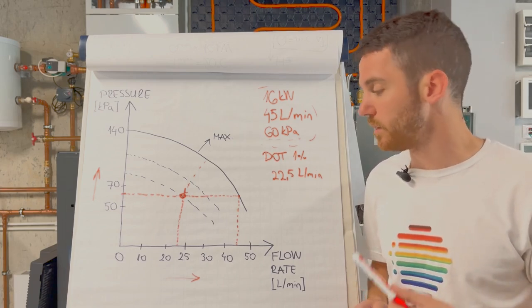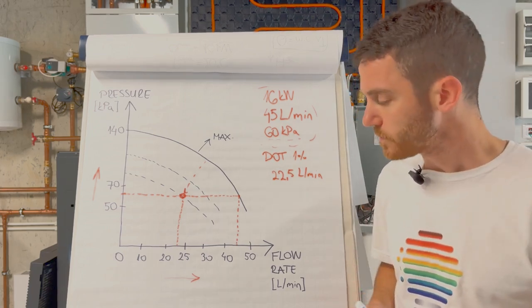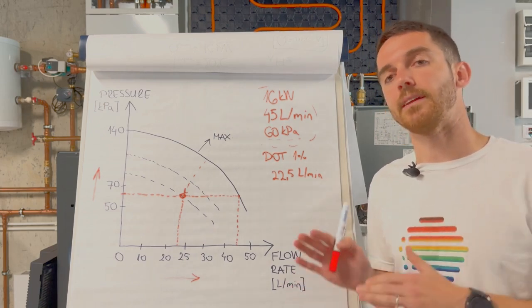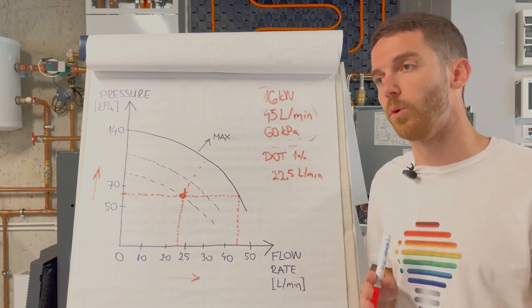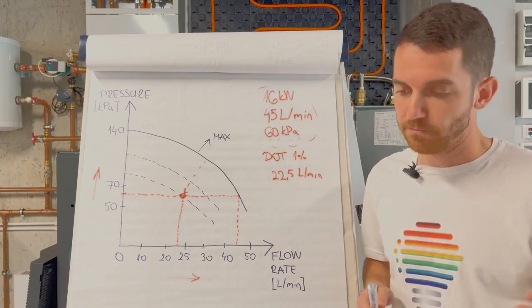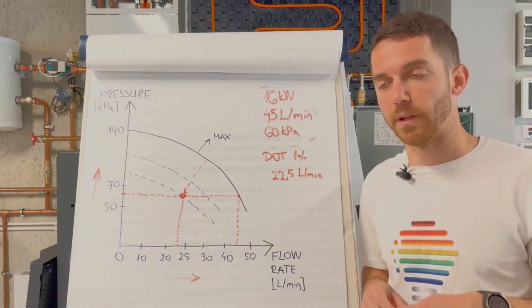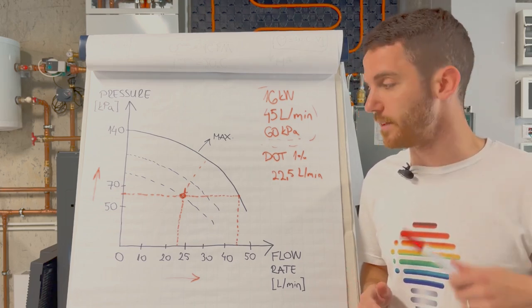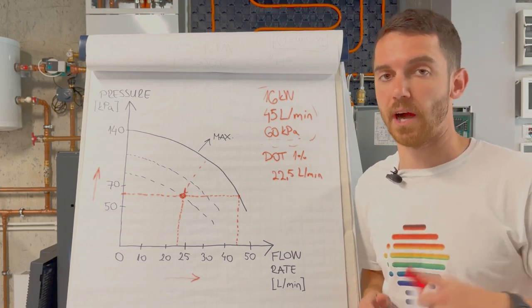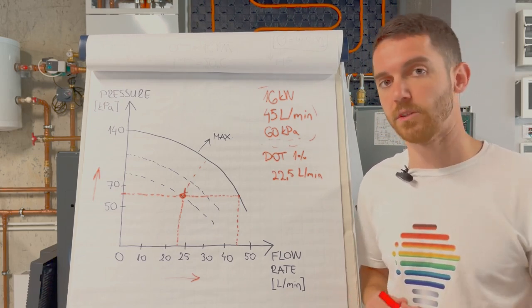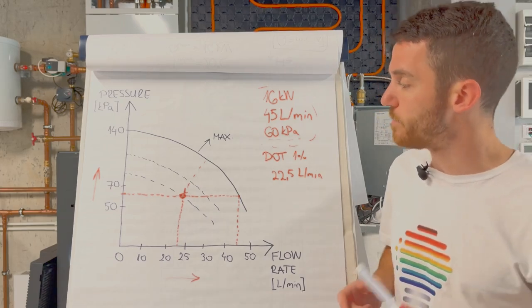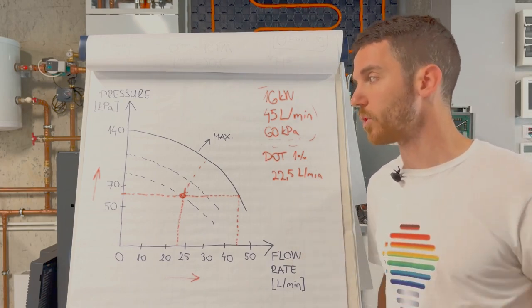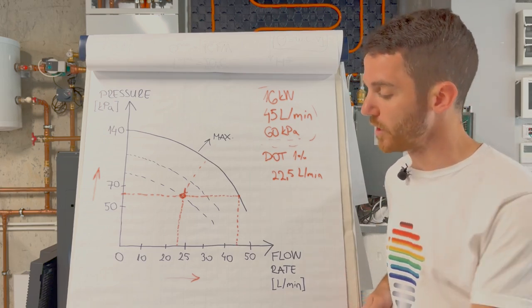And in my opinion and experience, if you cut off your system with buffer, you can really hard maintain flow rate on both primary and secondary side. For some specific examples probably you will help yourself with buffer. But with 90 percent or more installations, especially if you have only underfloor heating or only radiators, so one zone, you don't need it. It's better to modulate with pump, it's better for efficiency, it's better for compressor, because this is why manufacturer put so capable pump.